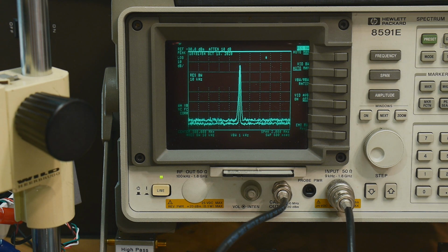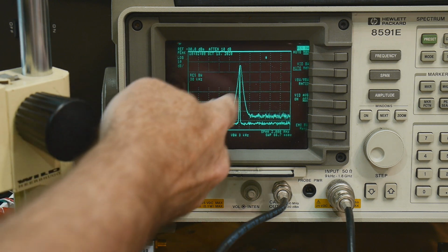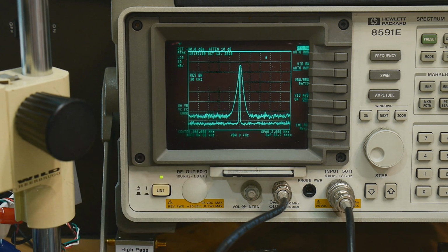So this is compared with 10 kilohertz. You can see that the filter got wider, but the noise level came up. And here, this is 30 kilohertz. So you can see it's much wider now, but the noise comes up. That's what I wanted to get across. When you increase the width of the filter, not only does your resolution go down, it actually integrates more noise, and so your noise level comes up.